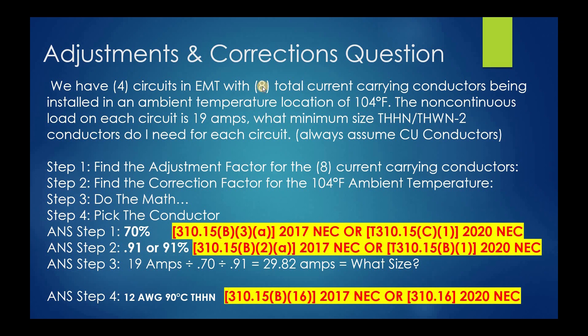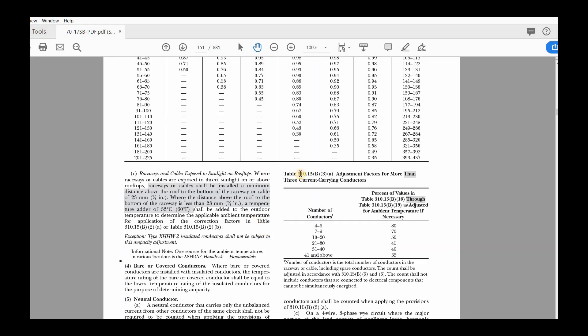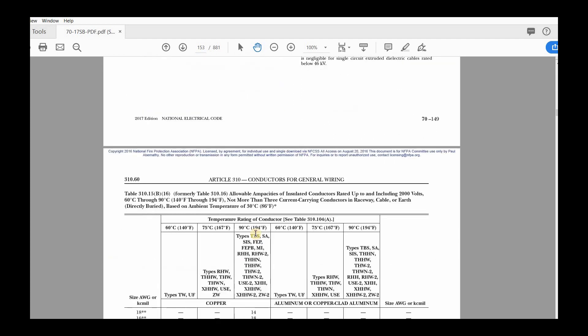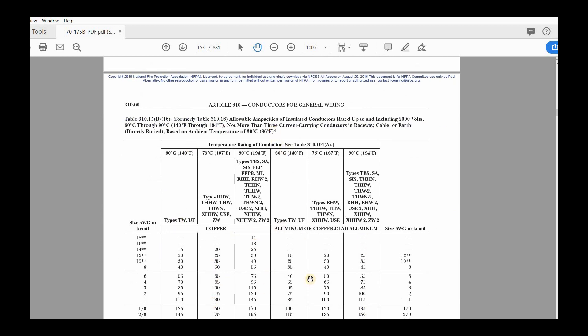The first thing I look at in this exam question: we have eight total current-carrying conductors. So Step 1 is finding the adjustment factor for eight current-carrying conductors. In the 2017 NEC, that's Table 310.15(B)(3)(a). This is the adjustment factor — many people call it the derating factor, which is fine — and it applies when you have more than three current-carrying conductors. The ampacity table is based on not more than three current-carrying conductors, so anytime I have more than three, I need an adjustment.